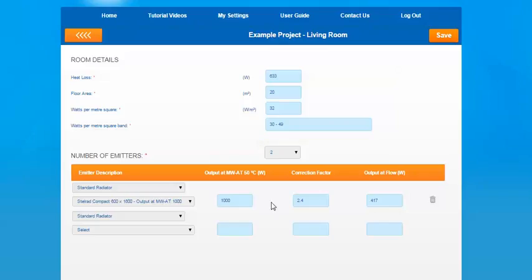As you can see from our previous example, the output has been pulled through and then a correction factor has been applied based on the heat emitter guide. Also, an output of flow has been applied to that emitter based on the conditions of the room and the flow temperature selected on the previous section.